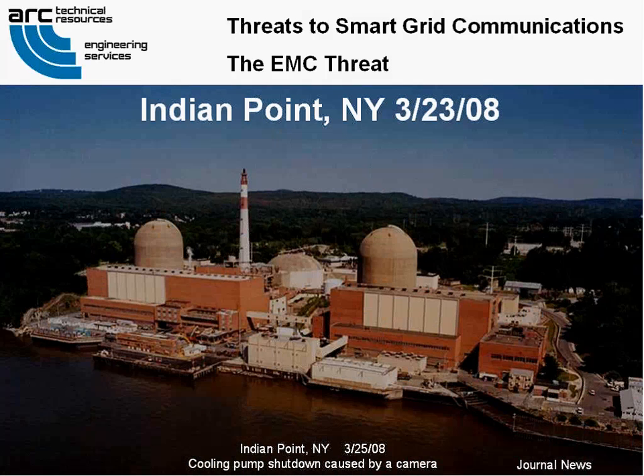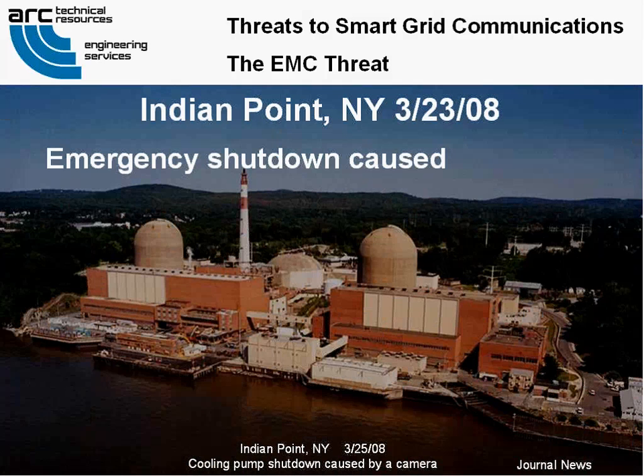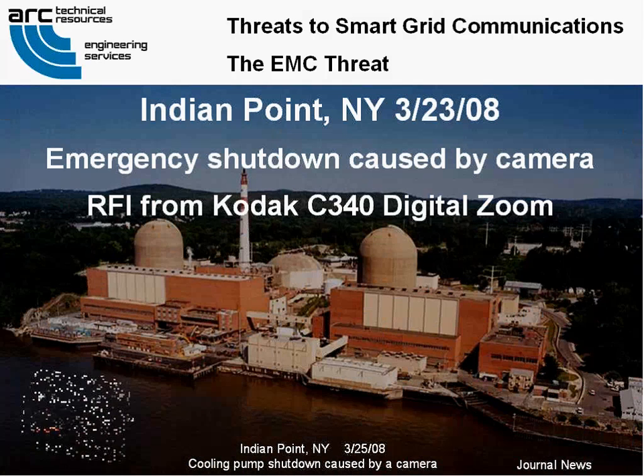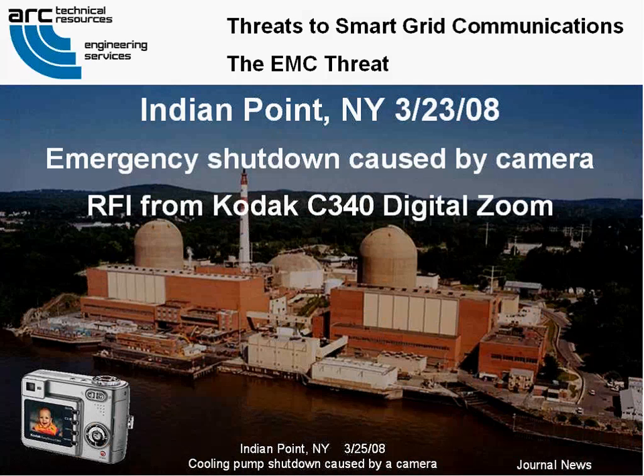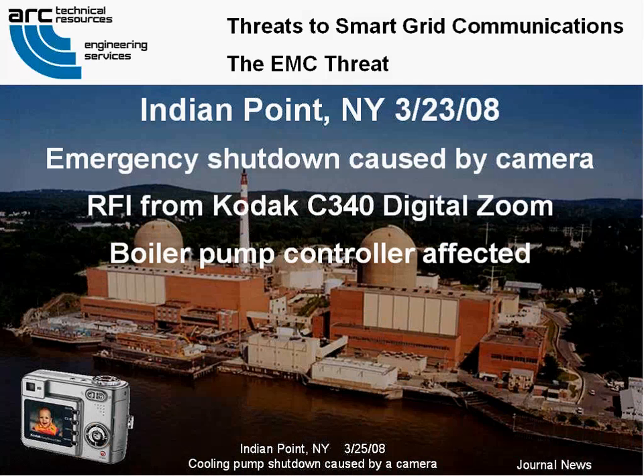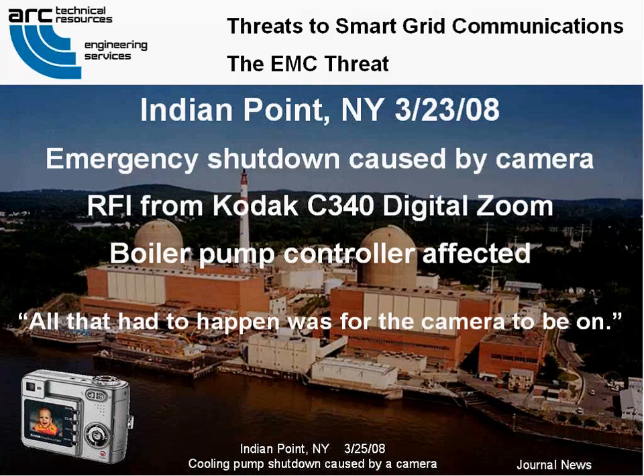Indian Point, New York, March 23, 2008. An emergency shutdown of a reactor at the Indian Point nuclear power plant was caused by signals from a worker's digital camera, the Journal News reported on June 11, 2008. Federal regulators said radio frequencies from a Kodak C340 digital zoom camera operated too close to a control panel interfered with a boiler pump controller that provides water to four steam generators. Quote, the direct cause was radio frequency interference from the camera, unquote, NRC spokesman Neil Sheehan said. All that had to happen was for the camera to be on.